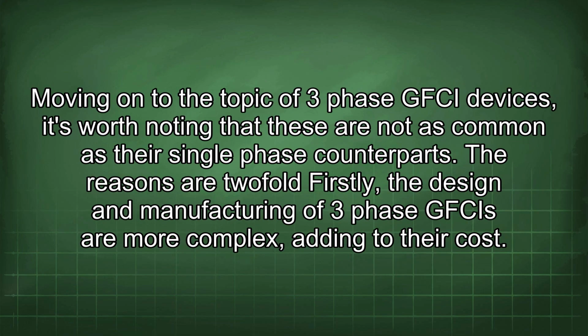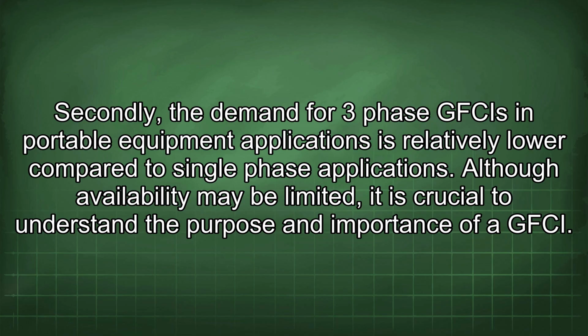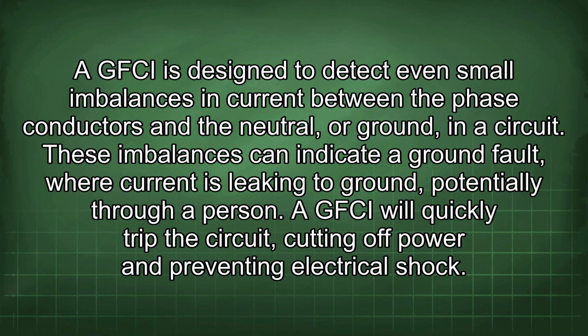Moving on to the topic of three-phase GFCI devices, it's worth noting that these are not as common as their single-phase counterparts. The reasons are twofold. Firstly, the design and manufacturing of three-phase GFCIs are more complex, adding to their cost. Secondly, the demand for three-phase GFCIs in portable equipment applications is relatively lower compared to single-phase applications. Although availability may be limited, it is crucial to understand the purpose and importance of a GFCI. A GFCI is designed to detect even small imbalances in current between the phase conductors and the neutral, or ground, in a circuit. These imbalances can indicate a ground fault, where current is leaking to ground, potentially through a person. A GFCI will quickly trip the circuit, cutting off power and preventing electrical shock.